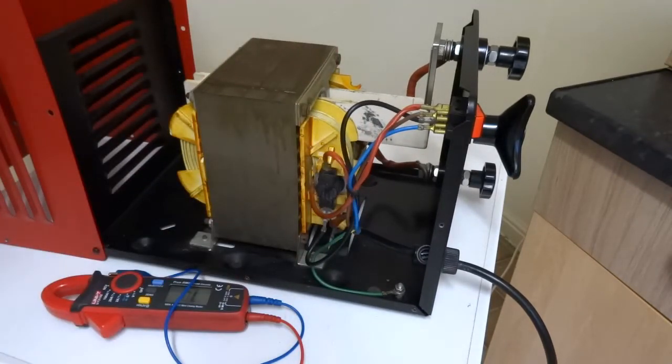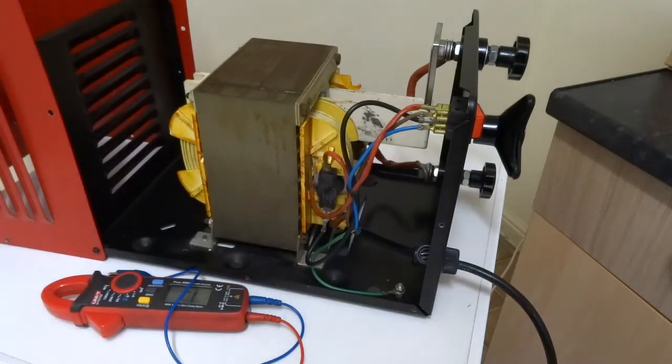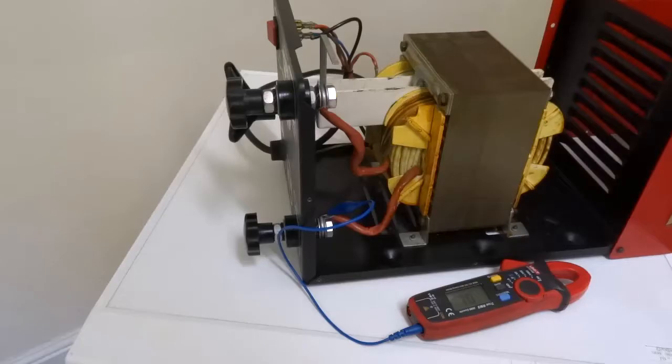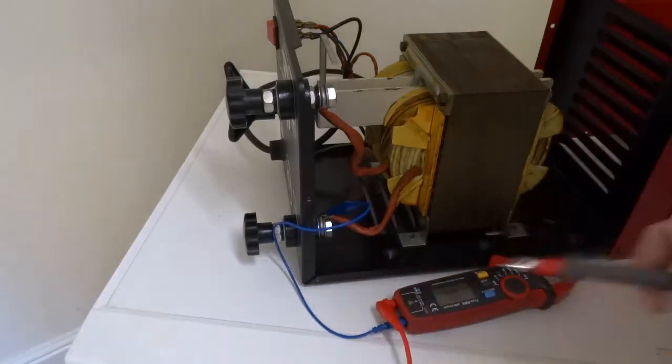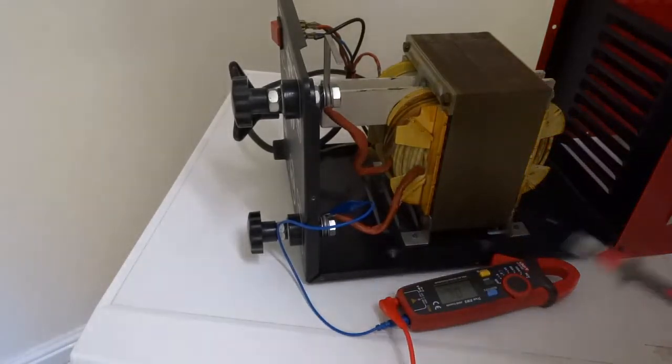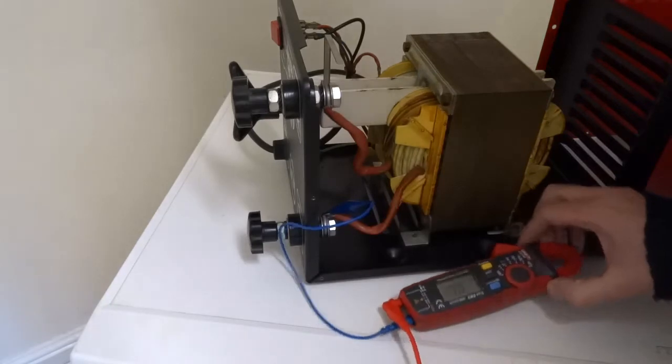I'll start the video, turn it around and test the secondary side. I'm going to do the same tests on the secondary side, just make sure the winding is intact and there's no leakage to earth, but this time I'm going to use a normal probe since it's easier.